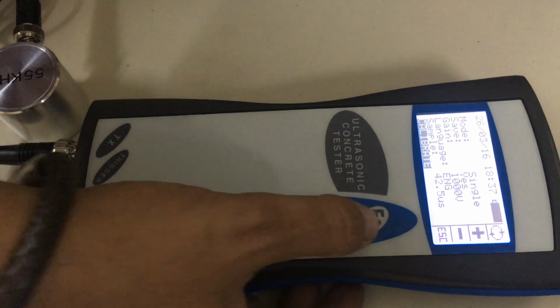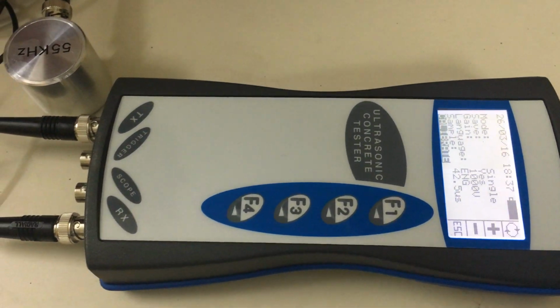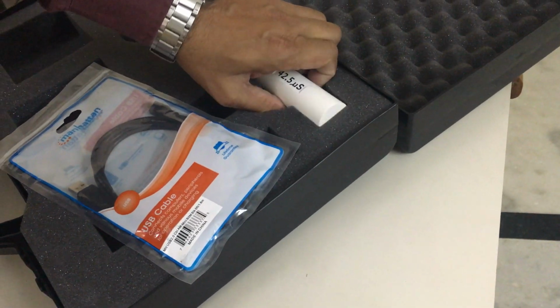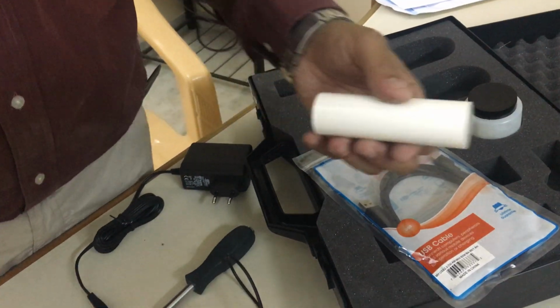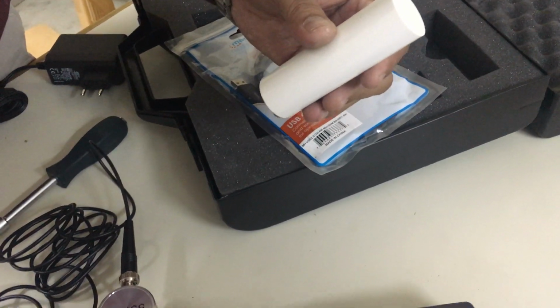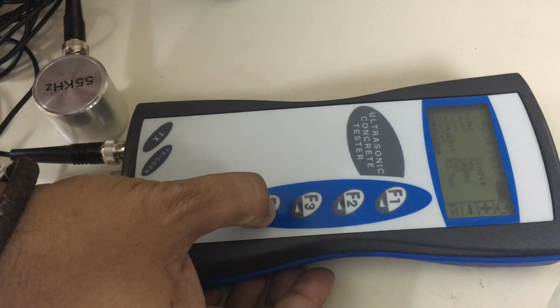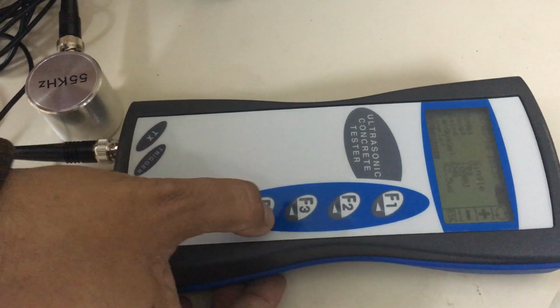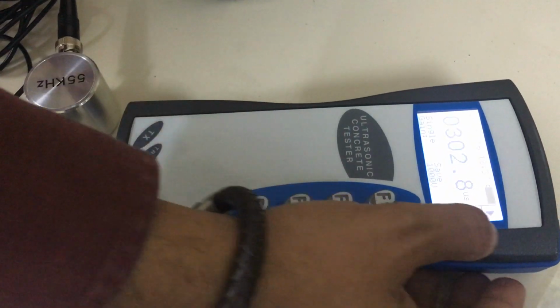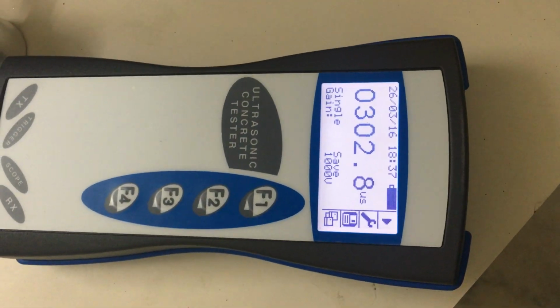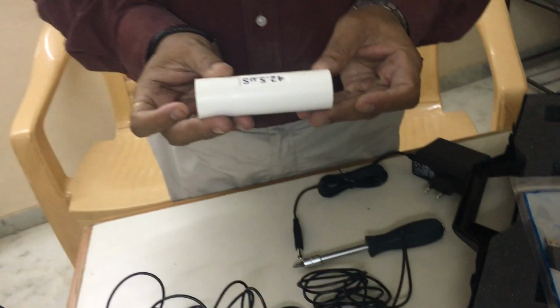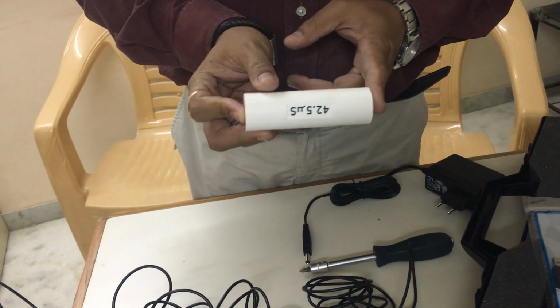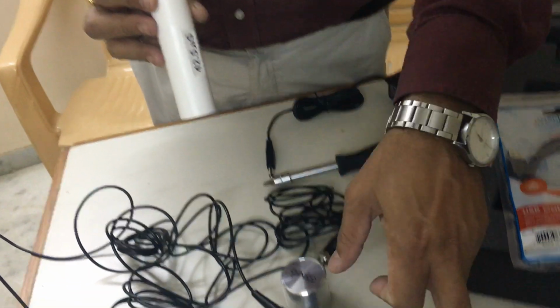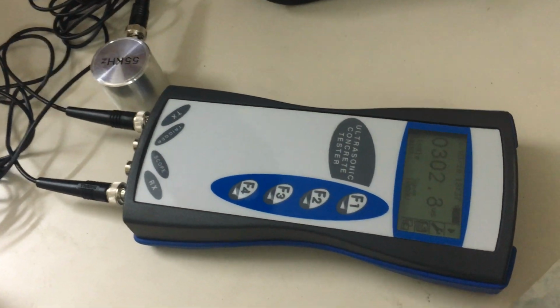Now this calibrate is whenever you are doing a fresh sample, it is essential you first verify your sample against your standard. I am not going to the calibration now, I am just doing one test. So I am escaping out of this menu by pressing the F4 key. Escape, F4. This is the main menu. If I press the F1 key, it will lead me to the start of the test. Now I am measuring the ultrasonic pulse velocity across the standard, so it should give me a time in microsecond exactly equal to 42.5 microsecond.